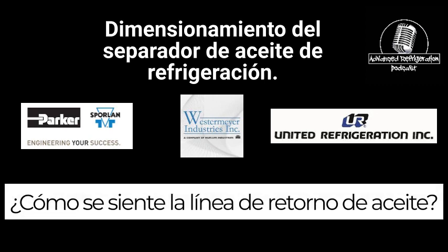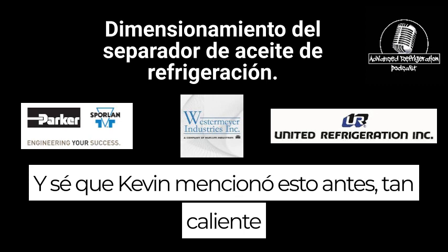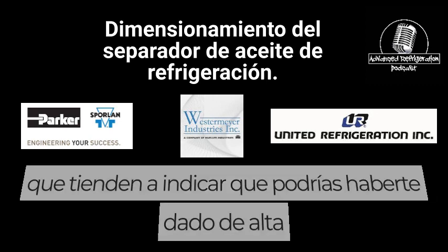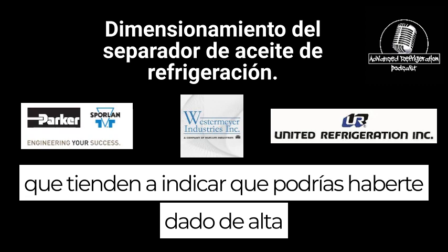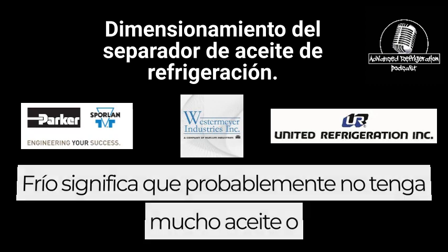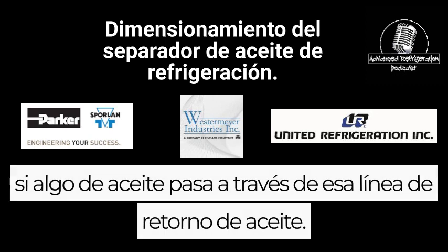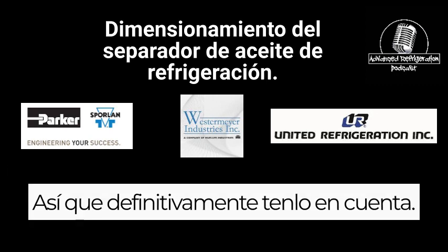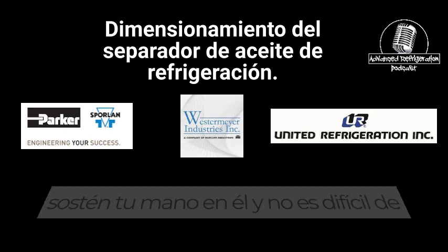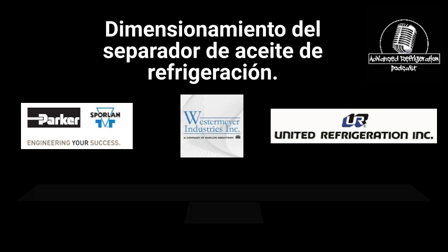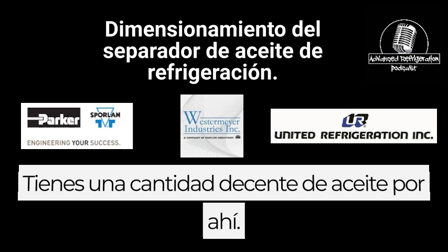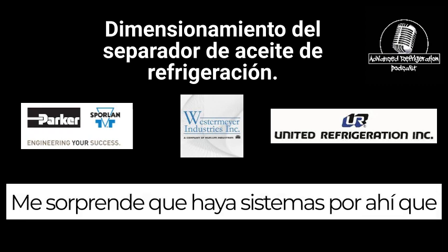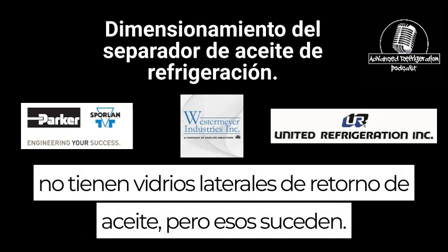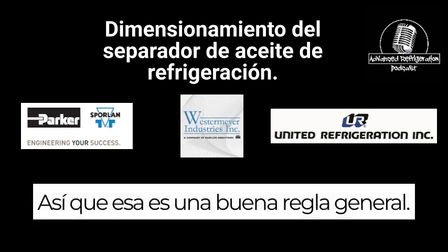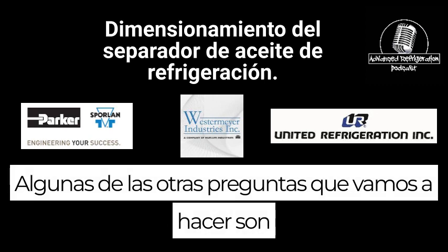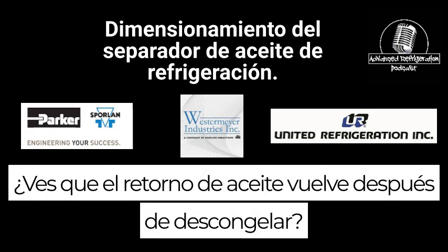What does the oil return line feel like? I know Kevin mentioned this before. If it's hot, that tends to indicate that you could have discharge gas blowing through that oil return line. Cold means that you probably don't have much oil, if any, passing through that oil return line. So definitely keep that in mind. And warm is really, as long as you can hold your hand on it and it's not hard to hold your hand on the oil return line, you've got a decent amount of oil through there. It surprises me that there are systems out there that don't have oil return sight glasses, but those happen. So that's a good rule of thumb. Some of the other questions we're going to ask is, do you see oil return come back after defrost?